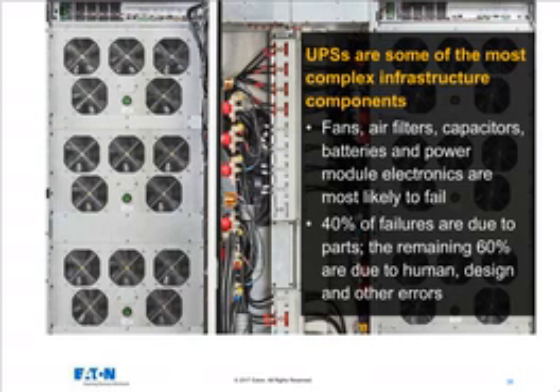Now, does that mean the computer is going to handle your UPS maintenance from now on and you or anybody else won't have to mess with it? No, that's not it at all. There's still going to be a human being in the process. But as you can see on this slide, UPS systems have mechanical devices like fans, air filters, contactors, and also other products that are similar to the tires and brakes on your car, like capacitors, batteries, power module electronics that are somewhat consumable and are the most likely items to fail.